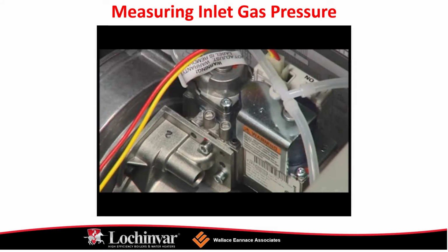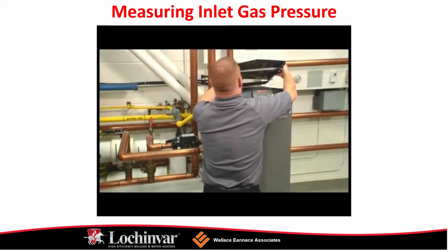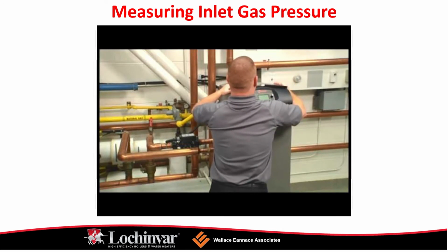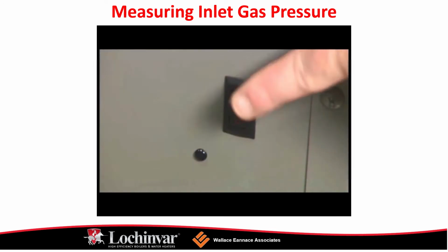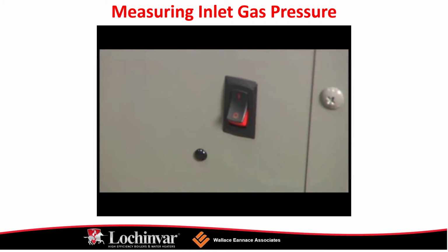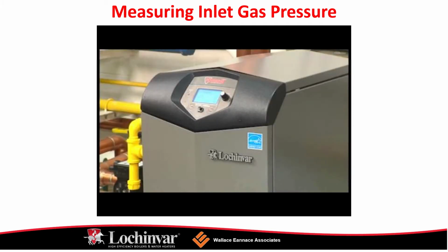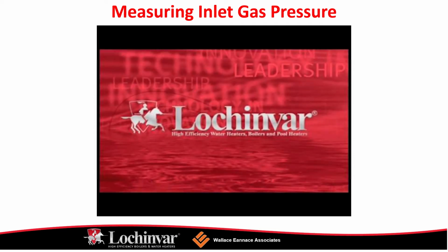Once the unit has modulated its firing rate up to 100%, observe the inlet gas pressure. If the inlet gas pressure is not within the proper range, contact the gas utility, gas supplier, or installer to determine necessary steps to provide proper gas pressure to the unit. If a pressure drop of more than 1 inch water column occurs, contact the gas utility, gas supplier, or installer as required to determine the necessary steps to correct the problem.